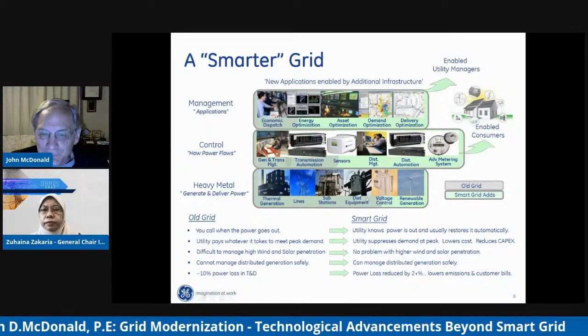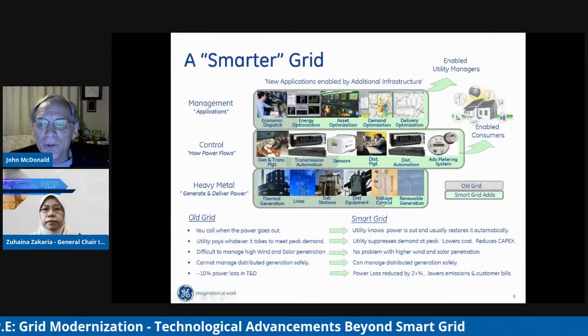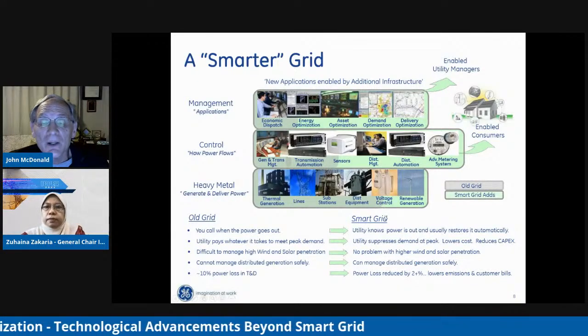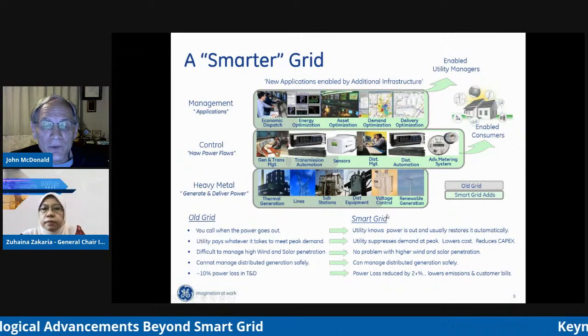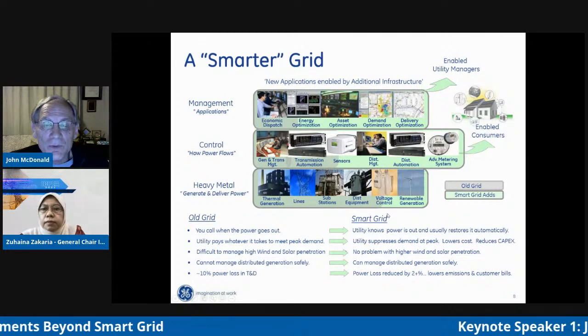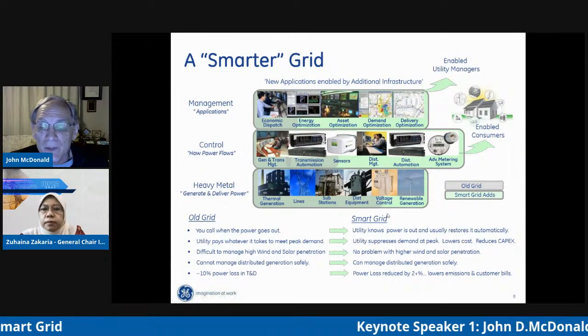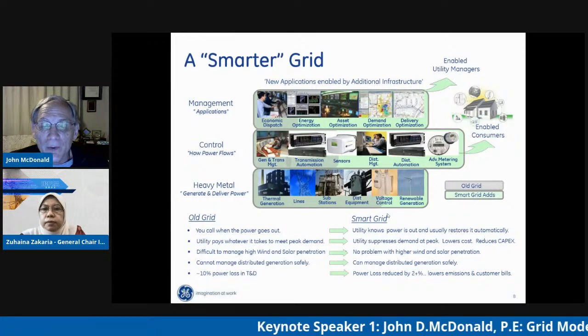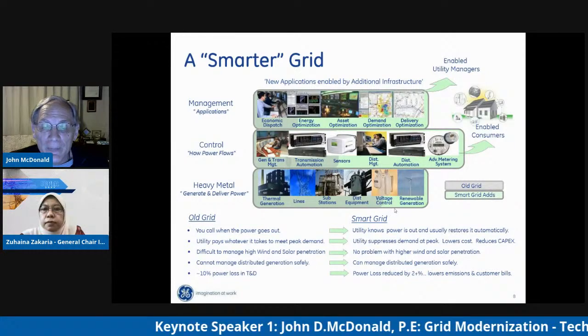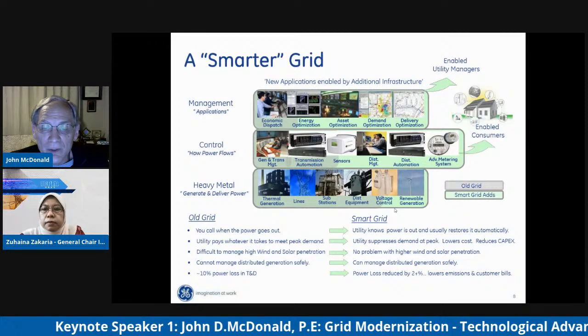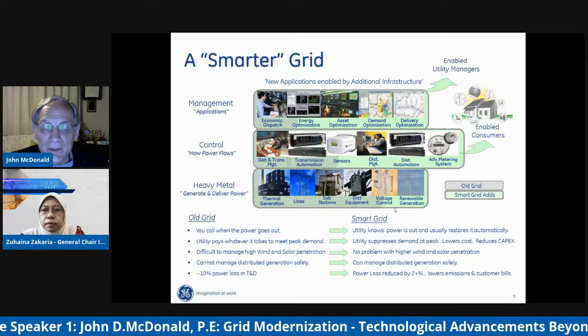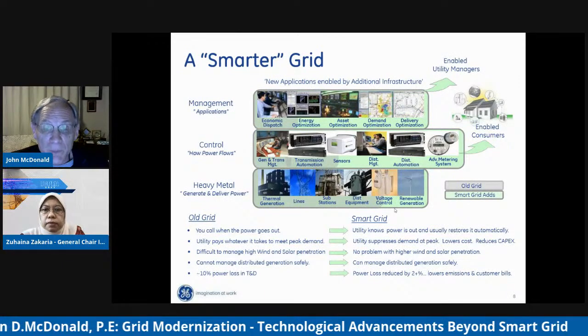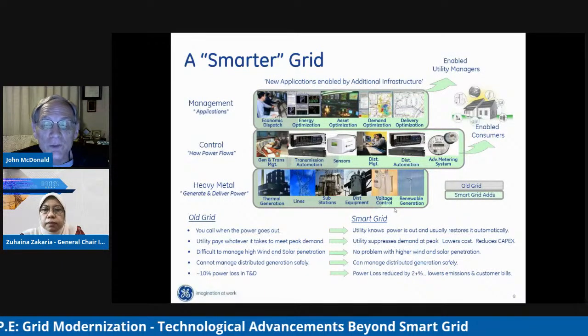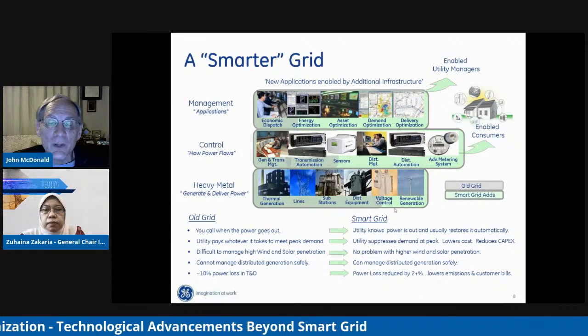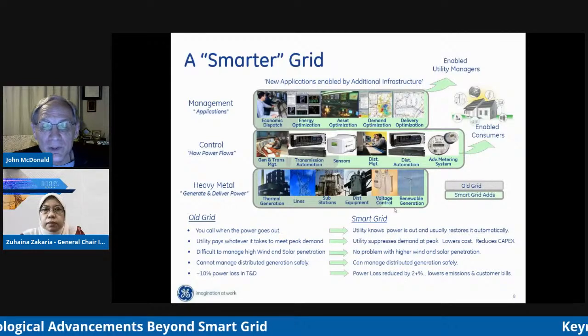You can see voltage control here is half shaded. We've been doing voltage control for a long time. Voltage is directly proportional to load, so one way to manage load—if it's increasing, like on a hot summer day, and getting close to the previous peak we don't want to exceed—we can lower the secondary voltage, which lowers the load.